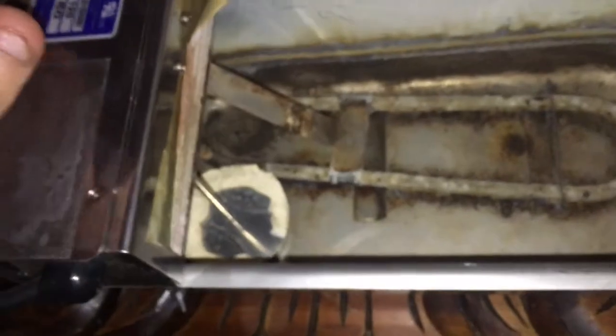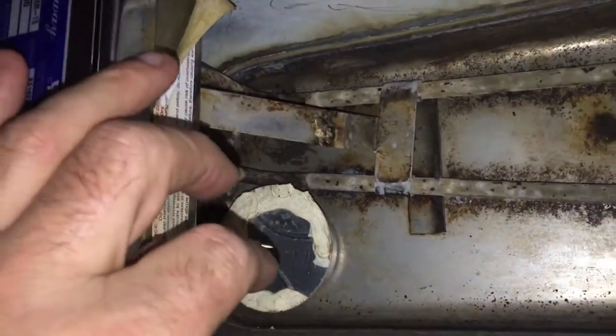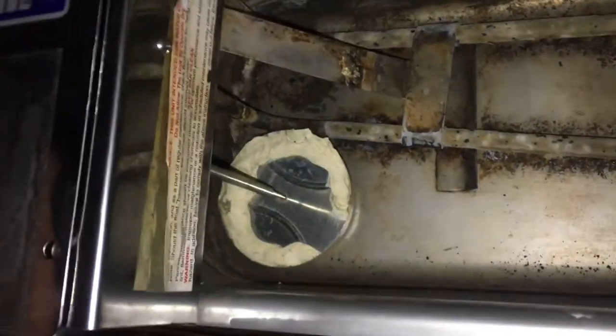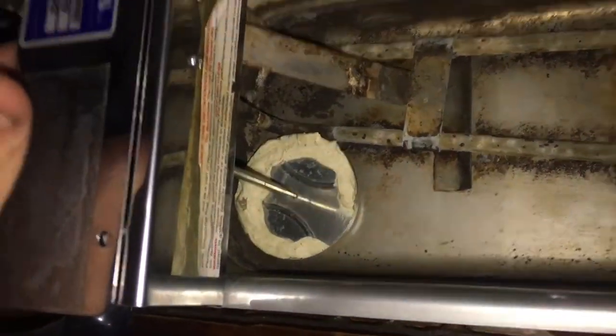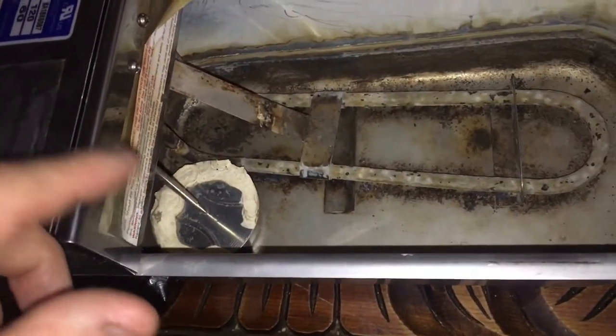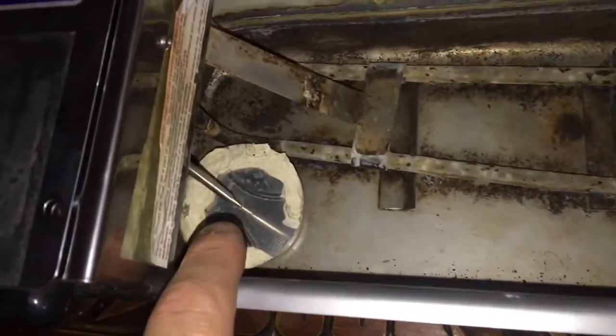This is the second one. The original one that was in an open air cooler — the float got all corroded within a year, under a year. They sent me a whole new one, and the second one I just put in there is already showing signs of starting to corrode also. It's sticking — the float's sticking on the bottom, like it's flat, and it sticks to the bottom sometimes.